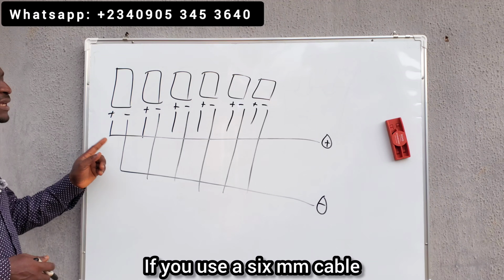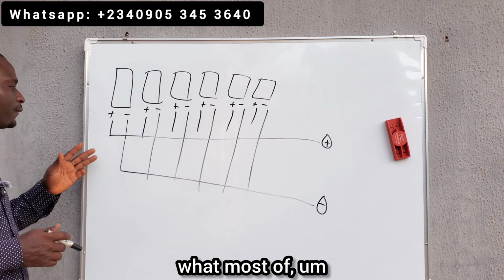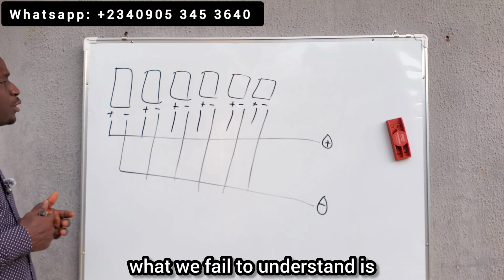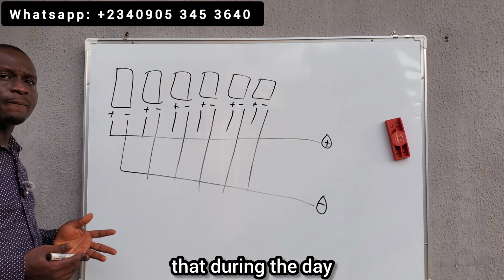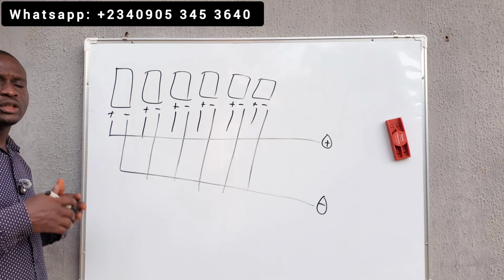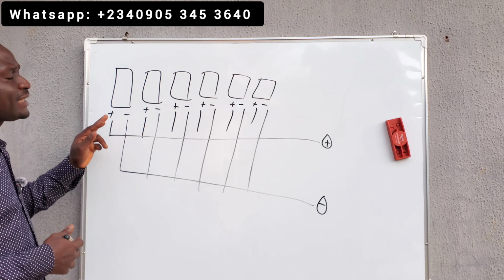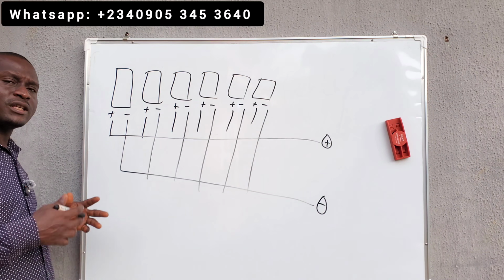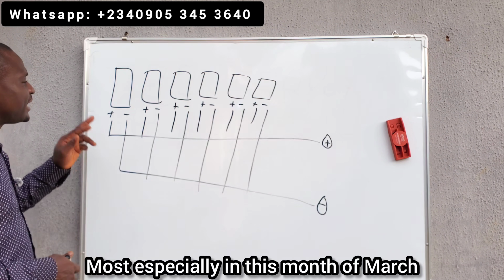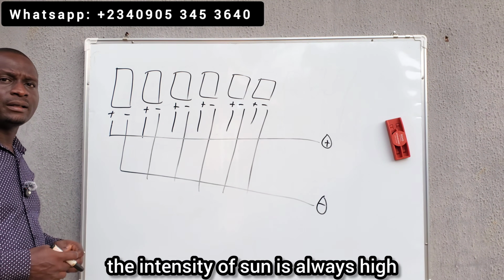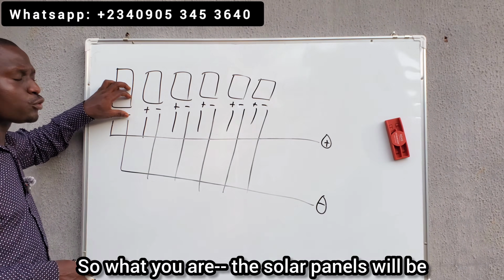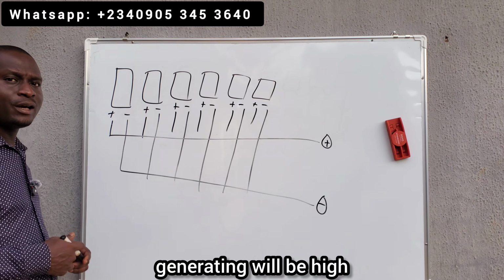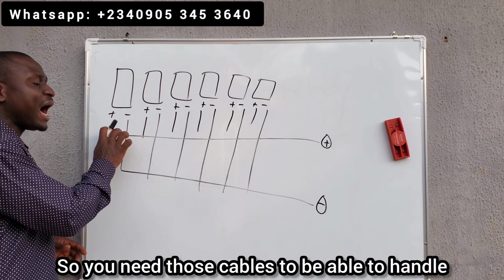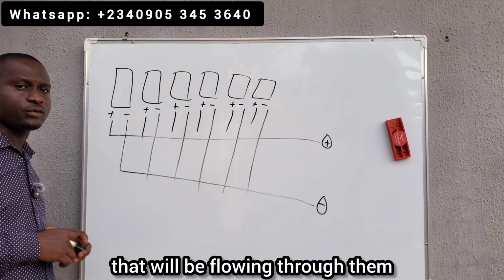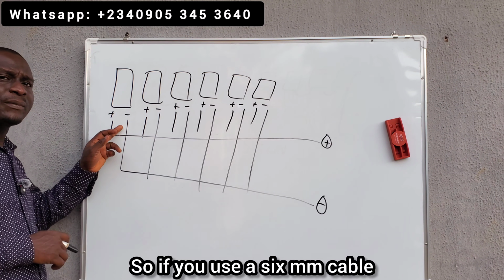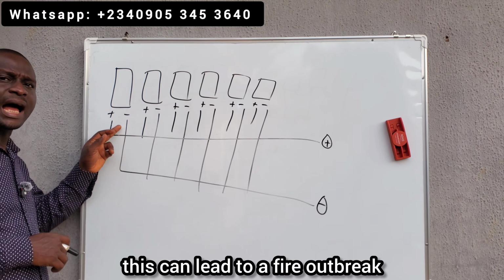If you use a 6 mm cable, what we fail to understand is that during the day, around 12 noon to 2 p.m., the intensity of the sun is always high, most especially in this month of March. So what the solar panels will be generating will be high, and you need those cables to handle that amount of current. If you use a 6 mm cable, this can lead to a fire outbreak.